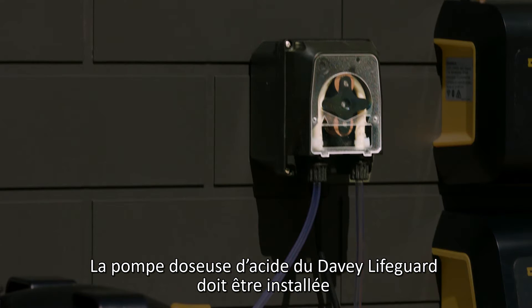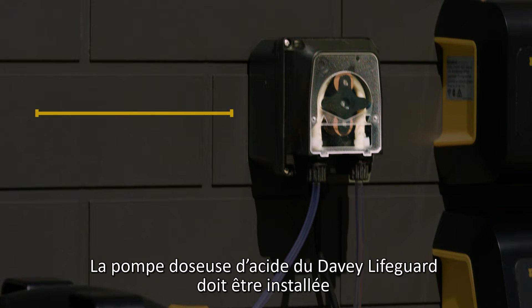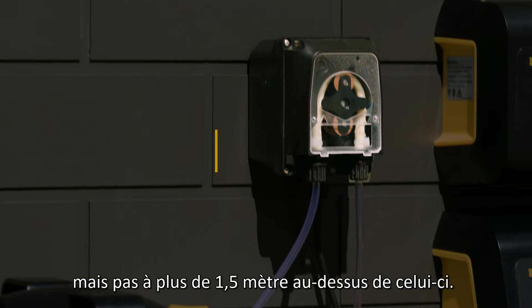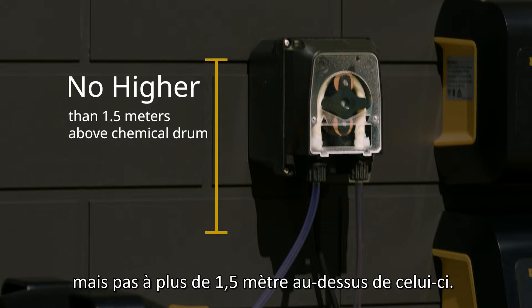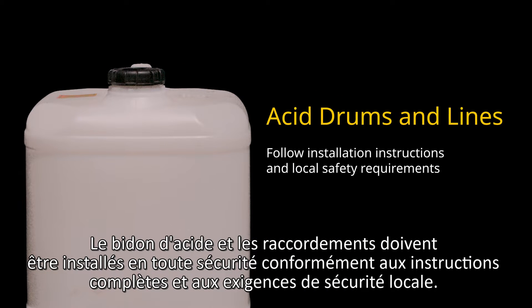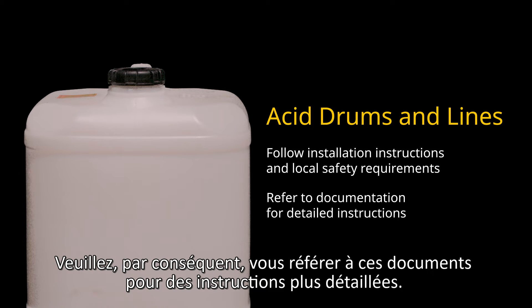The acid dosing pump on the Davey Lifeguard needs to be installed a minimum of 2 metres away from the chemical drum, but no higher than 1.5 metres above it. Acid drums and lines must be installed safely in accordance with the full instructions and any local safety requirements, so please refer to these documents for more detailed instructions.